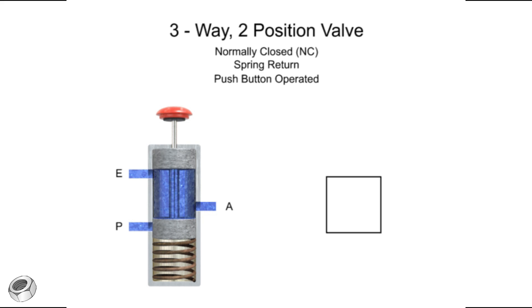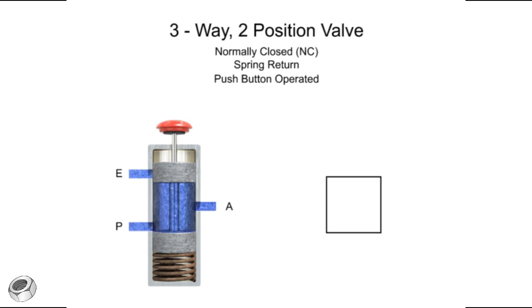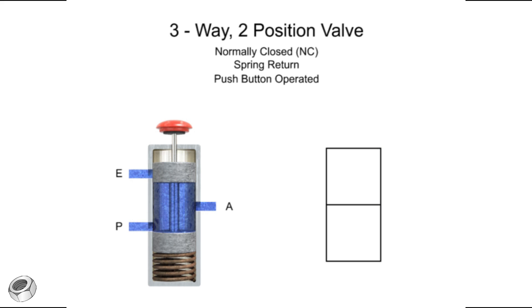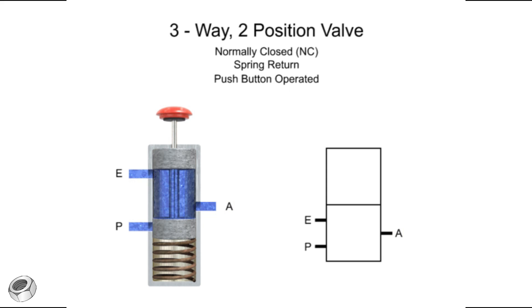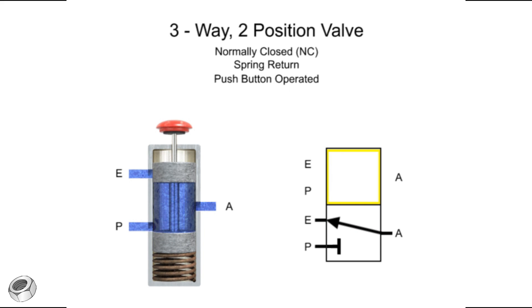The most important applications in fluid power for three-way valves are for directional control. Here we have a typical three-way valve with two operating positions. This valve has an inlet port P, exhaust port E, and output port A. In its normal position, inlet port P is blocked and outlet port A is connected to exhaust port E. The second position allows fluid to flow from pressure port P to outlet port A and blocks exhaust port E.